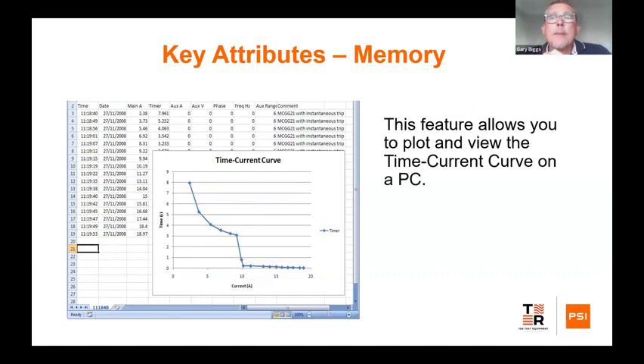Another key attribute with the memory is it allows us to store the values when we test at different points on a relay. So if you've got a 5 amp relay, for example, you'll test at half rated, you'll then test at full rated, you'll test at 2 times, at 3 times, and what you've got is you would then be able to plot that on a graph.